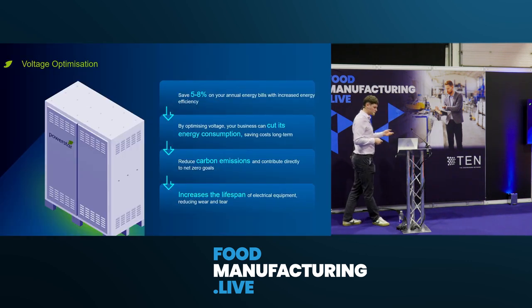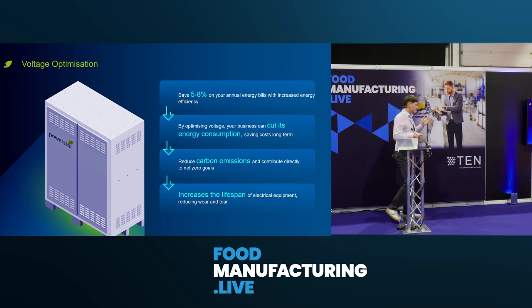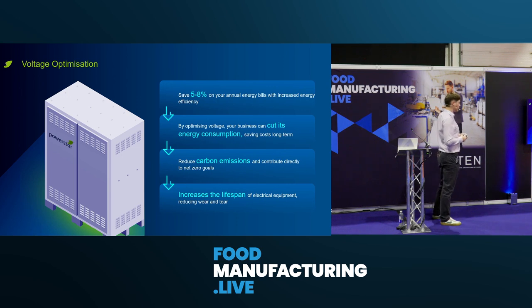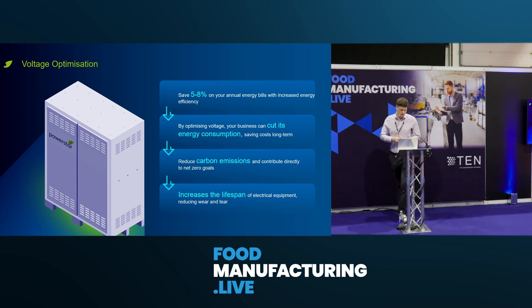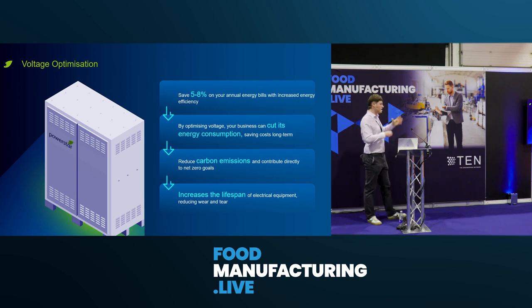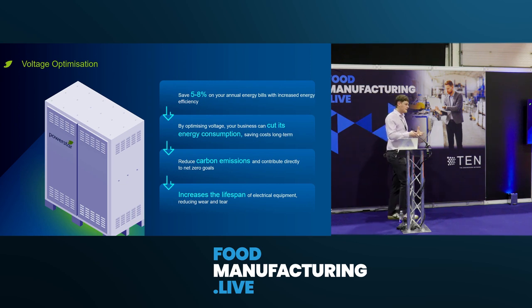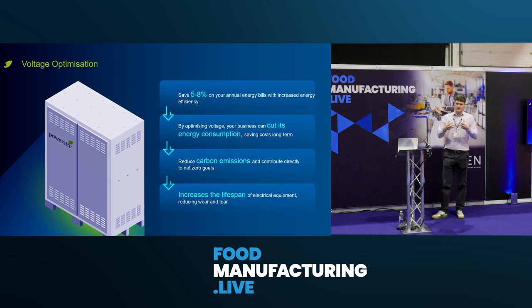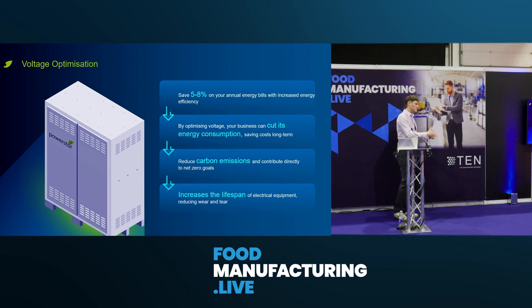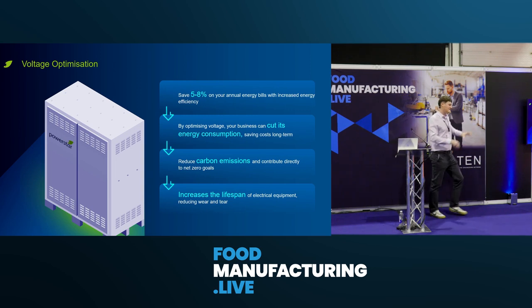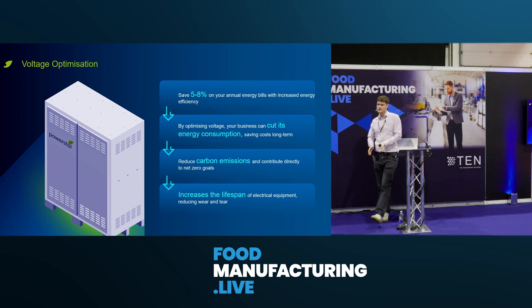So, just talking on VO, we're going to do a little bit about how it works. This talk is predominantly VO focused, but we are going to spend some time on BESS and transformers as well, as quick as we can. So, like we mentioned, 5 to 8% of your energy bills. So that's a reduction in kilowatt hours. Now, it's not the device itself saving you the energy. What it is, it's the device regulating the voltage, making sure that it's at its most efficient point for the equipment on site to work most efficiently. So the energy saving actually comes from the devices, the drives, the motors, working within their most efficient parameters, not the device itself. It's the impact of what that does. If you asked anyone years ago, they said, no, it's the voltage optimization device that saves you the energy. It's not. It's the efficiency that it brings for the equipment.